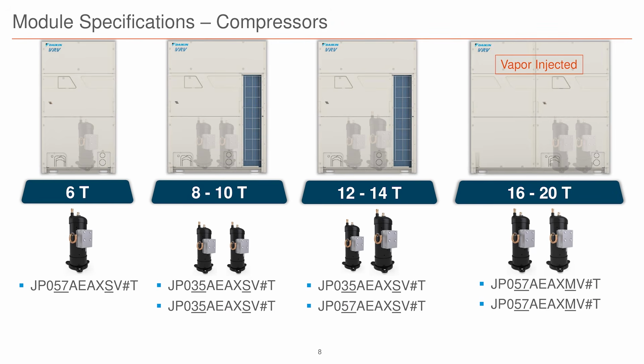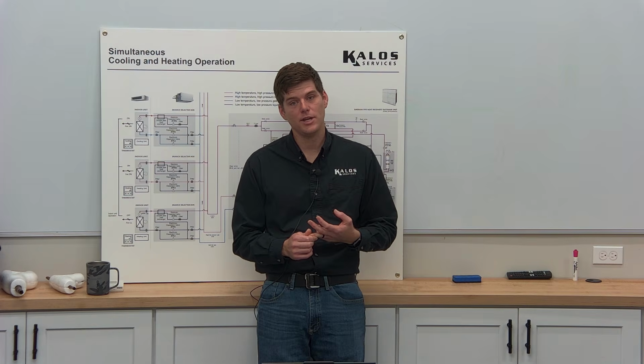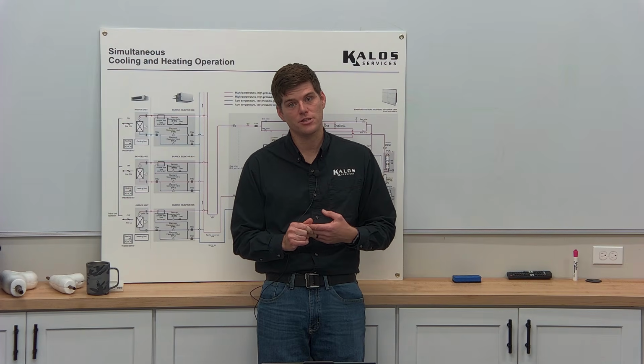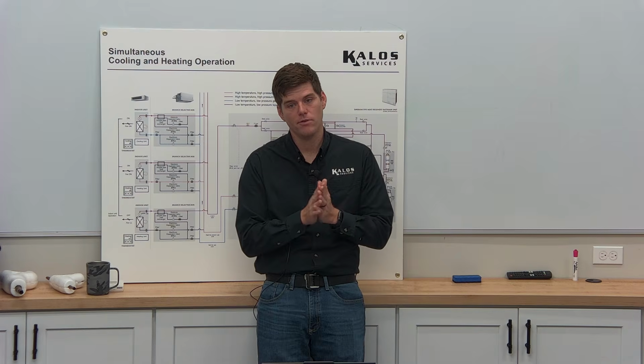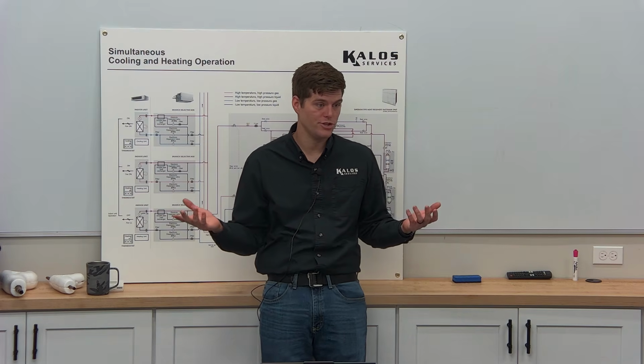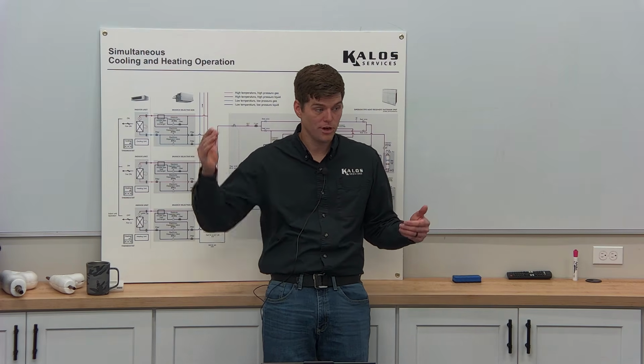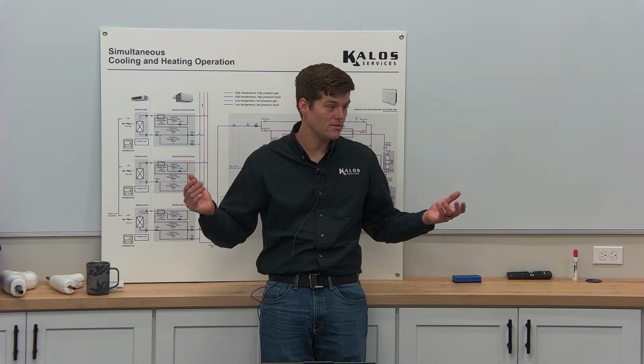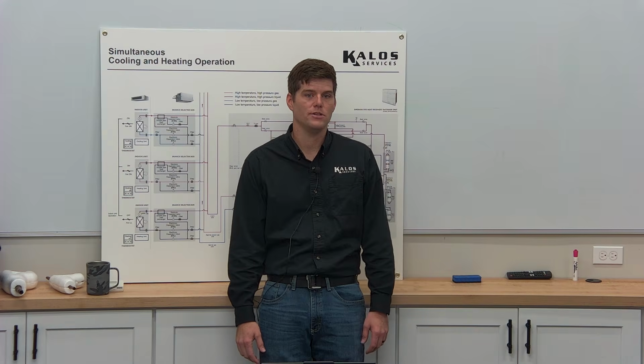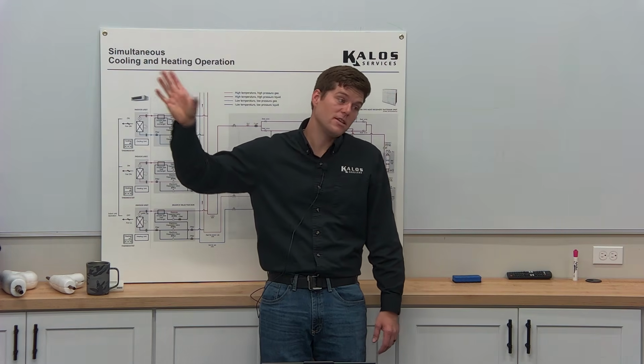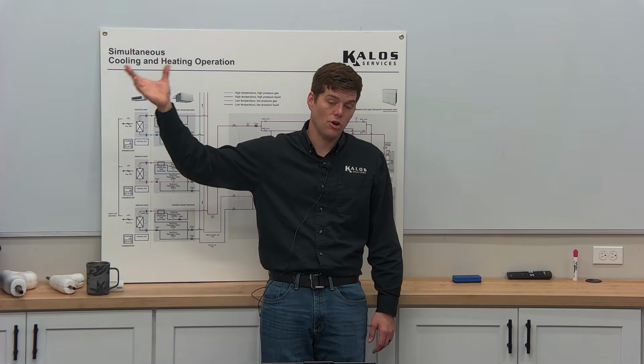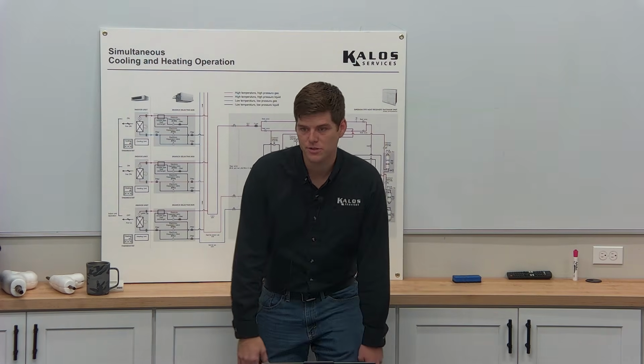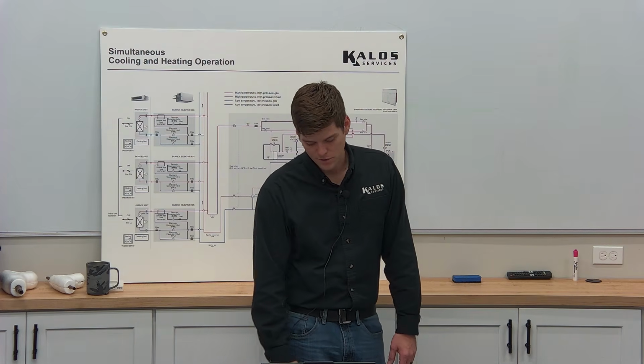So they're the same compressors in those? There are 3 types of compressors. There is the 57, as you see on that first one under the 6-ton. There is the 35, and then there is the 57, which is actually vapor injected. And so as we get into the realm, which is on the far end of that vapor injection side, that's when we get into the fun realm of compression ratio. Brian had a talk with you guys recently about compression ratio, right? Vapor injection just helps bring that down in low ambience and high ambience and whatever scenarios that you might find yourself in. So we will dive into that. But it does exist, right? So VRF, VRV, you'll find that a lot of these larger tonnage systems have vapor injection on the compressor itself, which is nothing crazy. And we'll talk about it in a service troubleshooting class that I have.